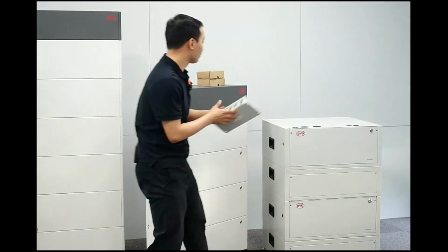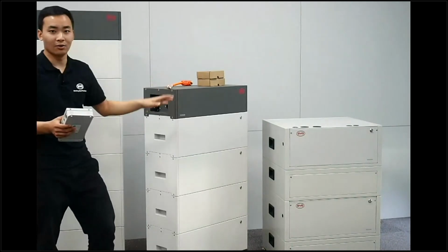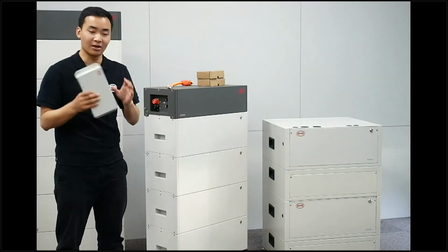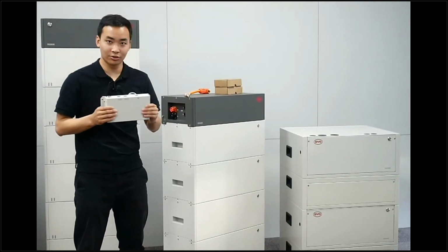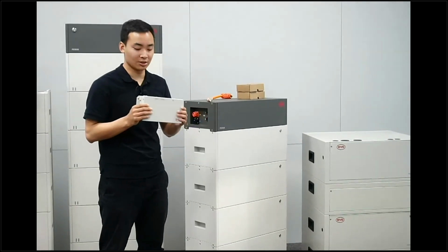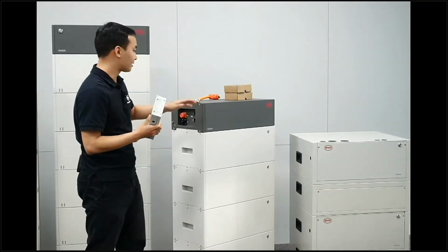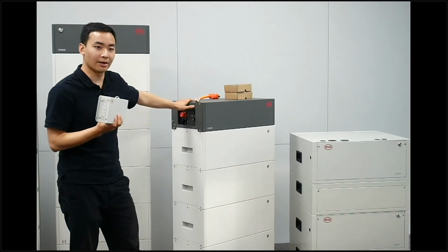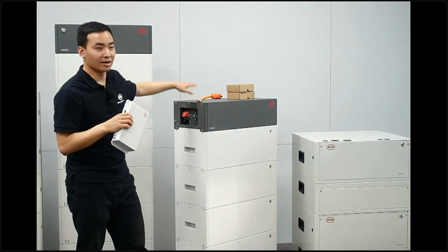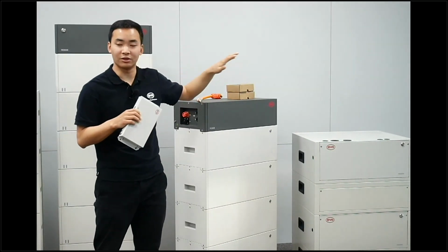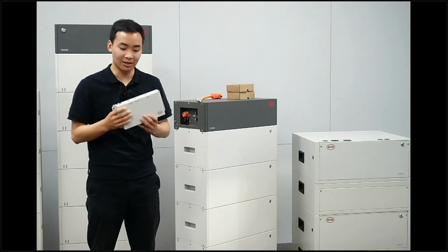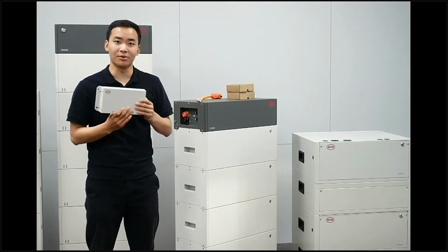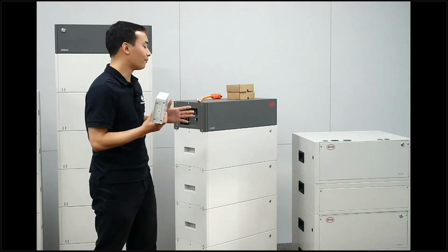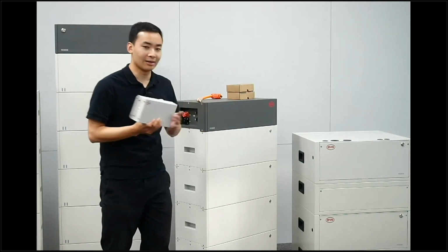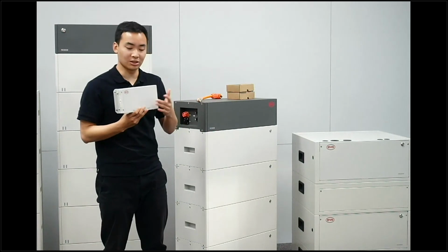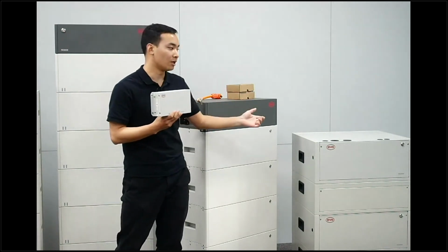The other thing for both LVL and LVS is they both have a BMU, which works like a control system for the whole system. If there's one battery for LVL, you need 1 BMU, and if there are 2, 3, 4, or even up to 64 systems connected in parallel, you still only need 1 BMU to control them. The LVS and LVL share the same BMU, meaning it can work for either one.